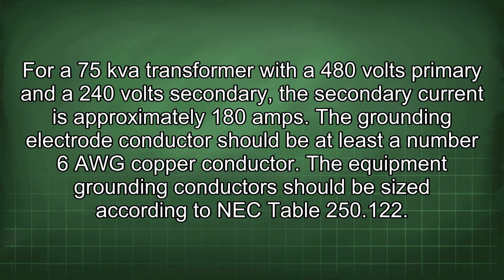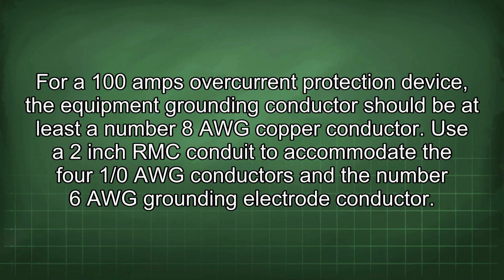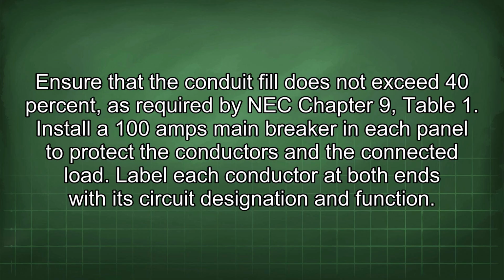The equipment grounding conductor should be sized according to NEC Table 250.122. For a 100 amps overcurrent protection device, the equipment grounding conductor should be at least a number 8 AWG copper conductor. Use a 2-inch RMC conduit to accommodate the four 1/0 AWG conductors and the number 6 AWG grounding electrode conductor. Ensure that the conduit fill does not exceed 40% as required by NEC Chapter 9, Table 1.